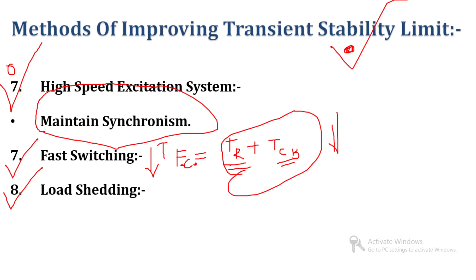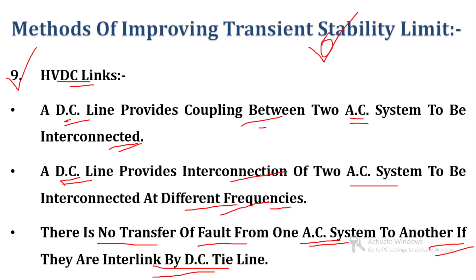Now the next point is the HVDC link. A DC line provides the coupling between two AC systems that can be interconnected, and that is known as the HVDC link. This DC line provides the interconnection of two AC systems which can be connected at different frequencies, and one of the major advantages of this HVDC link is that there is no transfer of fault from one AC system to another AC system if they are interlinked by a DC tie line. If there is no transfer of fault, there is no kind of interlink disturbance, because the two AC systems are connected by a DC line. In this manner we improve the transient stability limit. So these are the methods of improving the transient stability limit.